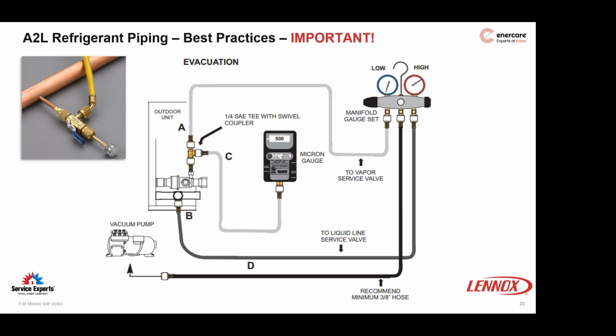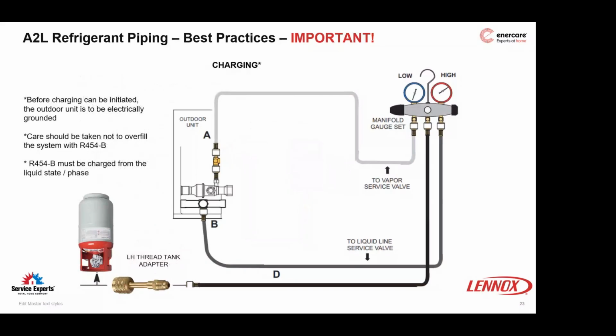There's a Schrader core removal tool. If you don't have one, they are a handy little tool. Once you've got a proper vacuum achieved and you're hanging out below that 1,000 microns, any additional refrigerant charge required can be added to the system to account for any additional piping lengths greater than 15 feet, and a coil that maybe requires some additional charge.